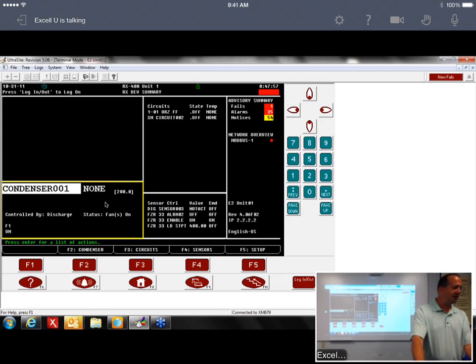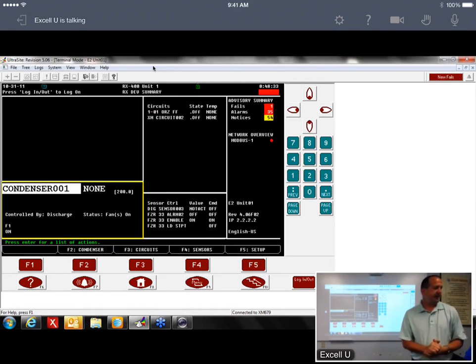Whatever you connect on the positive at the device, at the E2 you just have to reverse it. That goes to negative. You've probably seen some Dixell devices already in some of the new stores on the chiller controller. The chiller expansion valve is a Dixell product. It's actually a superheat controller, XEV 30 or XEV 22. It'd be the same way. The polarity there is reversed. Like I said, that's just one thing to keep in mind.